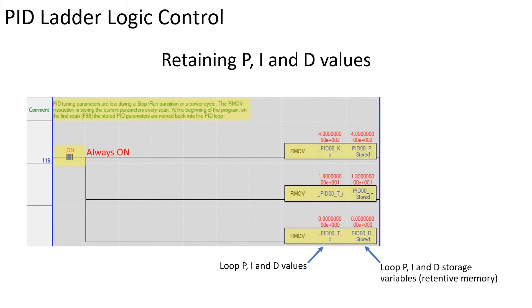The real move instruction is used to constantly move the operational PID values to retentive memory. These variables are created in K memory by the programmer. The values are constantly written to retentive memory in the event manual tuning adjustments take place during operation.